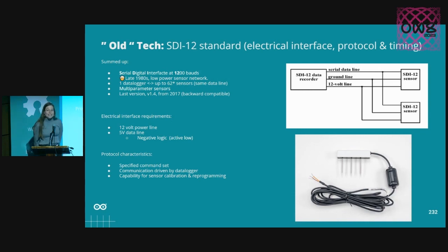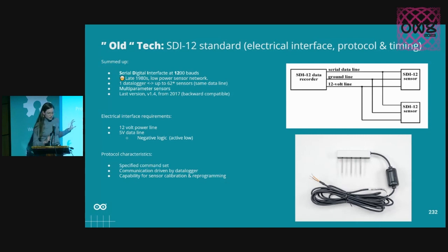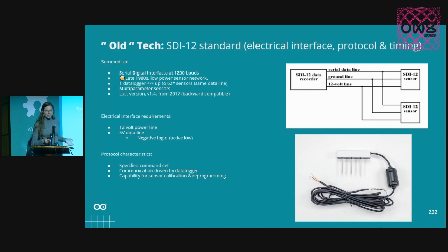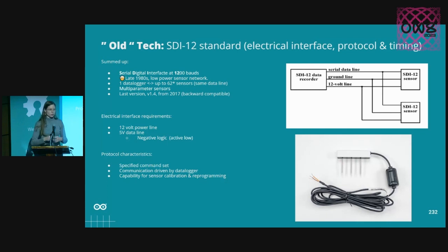Let's break the talk down. First, the old tech part. I'm referring to the SDI-12 standard, which includes the electrical interface, the protocol, and the timing. To sum it up: SDI-12 is short for Serial Digital Interface at 1200 baud — so it's a very slow communication protocol. It was born or standardized in the late 80s. It was developed to be used mainly in agriculture for field monitoring or large area monitoring, with the idea of having a low-power sensor network, which in the late 80s was mainly wired.